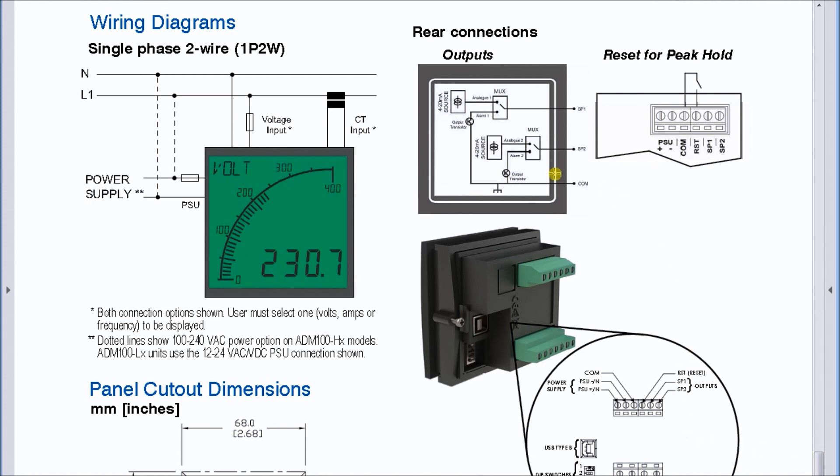If we look at the wiring diagram itself, we have a single phase two-wire configuration. If we have the DC model, which we do, then we bring in the DC here. If we have the AC, we can go anywhere from 100 to 240 and usually we just bring it through the line down to the unit.